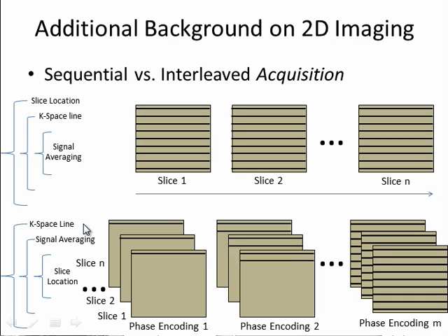For interleaved acquisition, we have a different ordering of the acquisition loops. The first phase encoding line could be up here or down here. It would be acquired — first slice location, inner loop. Then we would go to the next slice, gather that phase encoding line, go to the next slice, gather that phase encoding line, then go to another slice location. Then we go to the next phase encoding, and we go to the next slice, doing any averaging on that line that we might need.